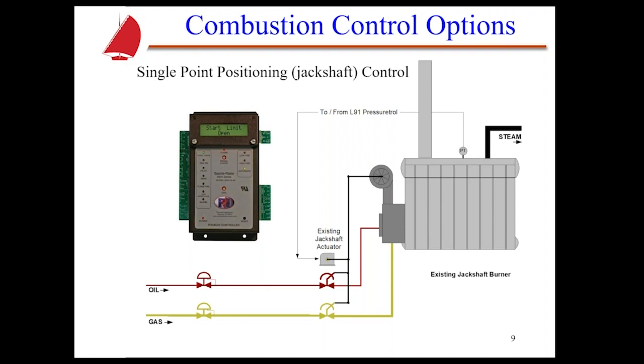And then once we have the burner lit off correctly, we can then release it through those dry contacts, the modulation to an external product like a Pressuretrol, for instance. And then we will start modulating around a set point that is set in the Pressuretrol. So that actuator or mod motor then will begin operating through that linkage, the gas valve and the oil proportioning valve, even though it may not be operating at that time on gas, and it will also be actuating the air damper at the same time. And that's the way so many systems operated for many, many years.